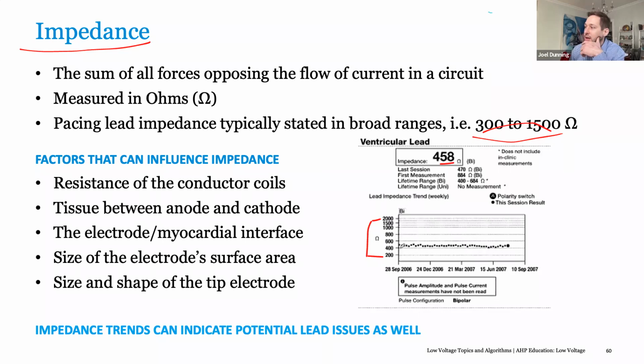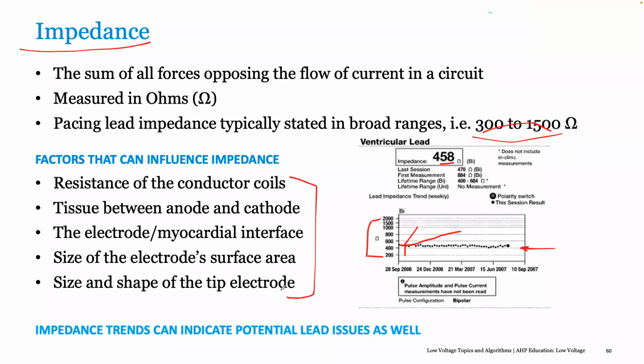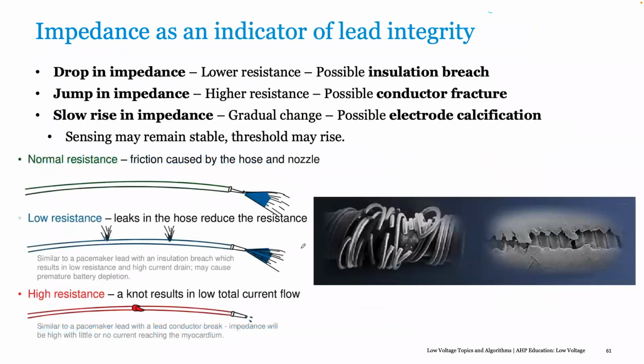If your impedance trend is consistently within around 450 ohms and it stays this way, that's generally a pretty strong indicator that the lead integrity is going well. If you see your impedance trend over time having a slow rise, or you see sudden jumps or drops in impedance, that can indicate that we have a much larger issue to address. So here it's describing the factors that can influence impedance. In general, what we're looking for is changes in impedance over time, because a lot of these things are controlled for. When we talk about impedance as an indicator of lead integrity, the big things we're looking for are drops, jumps, or slow rises or falls in impedance, indicating possible issues.